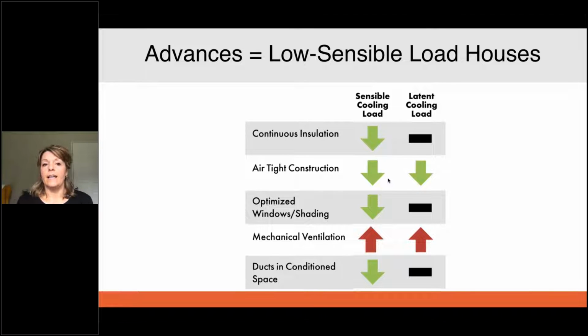Advances in building construction are resulting in low sensible load homes. So a lot of times when someone talks about a high performance home, low sensible home, or low load home, it really means low sensible load homes. Construction practices like continuous insulation, airtight construction, better windows, and ducts in conditioned spaces all reduce the sensible load on the house - the temperature we feel - but ultimately might not reduce the moisture load. So remember, a low load home really means a low sensible load home, not low latent load.